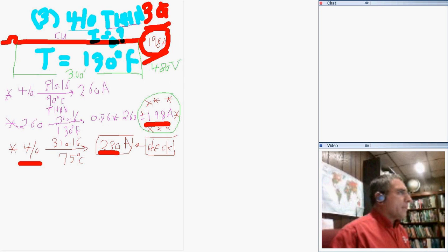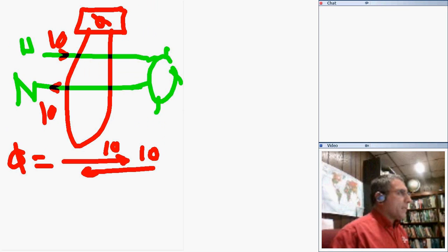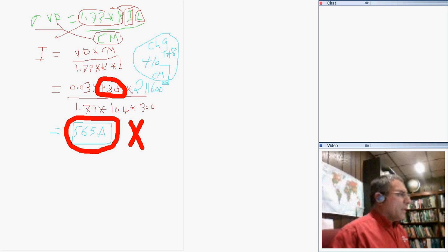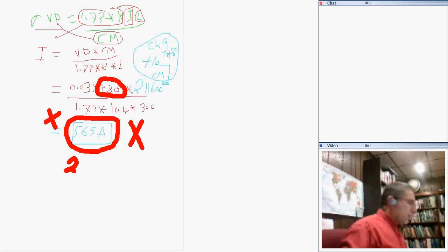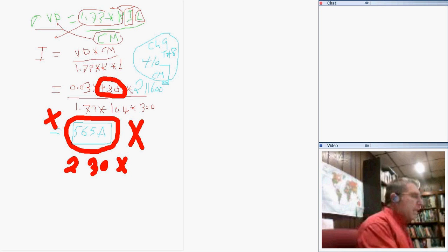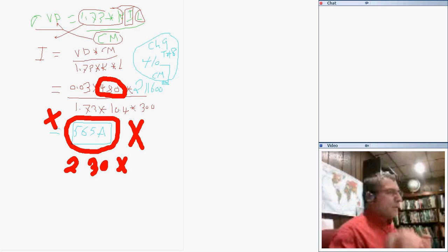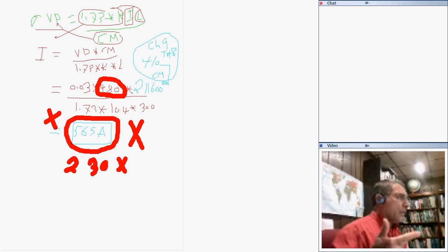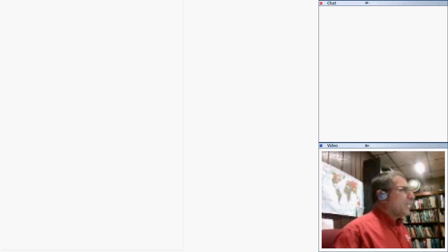So anyway, I thought the example was off the wall, but it really emphasized the point. You can't use 565 amps, the same way you can't use it because the conductor is limited to no more than 230. Guys, any questions? So the key point is, when you size conductors, you choose the conductor by the amps, the smallest amps or the largest conductor size.